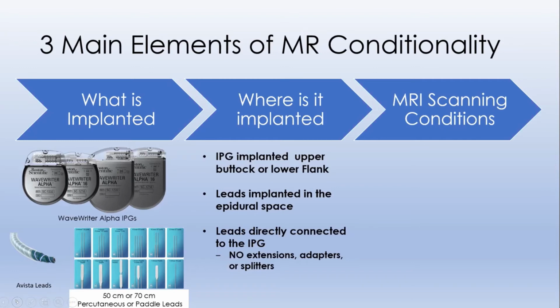And the last of the three elements is the MRI scanning condition. So we have to have a 1.5 Tesla scanner. We have to take into account the radio frequency power limits, that is the SAR value, which decides that. And also we have to take into consideration the active scan time limits, which is 30 minutes.